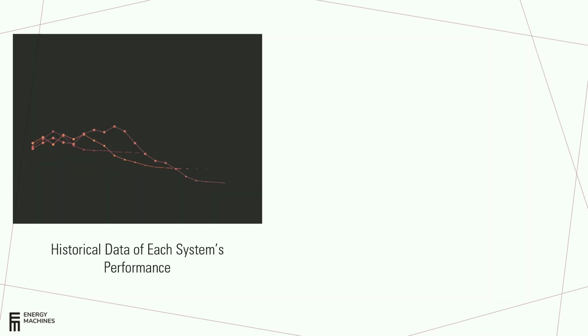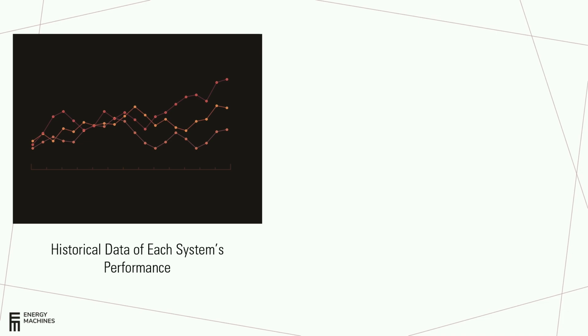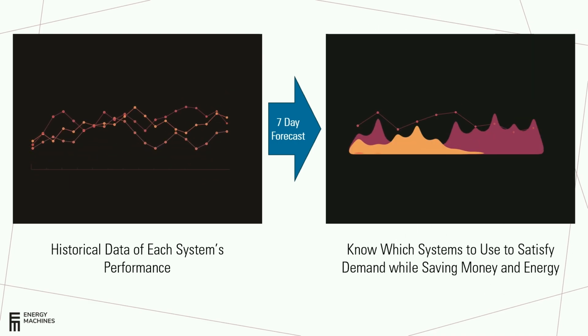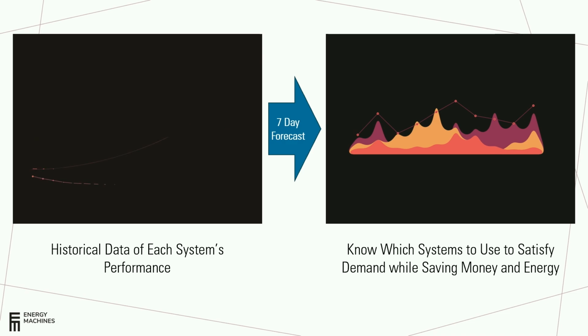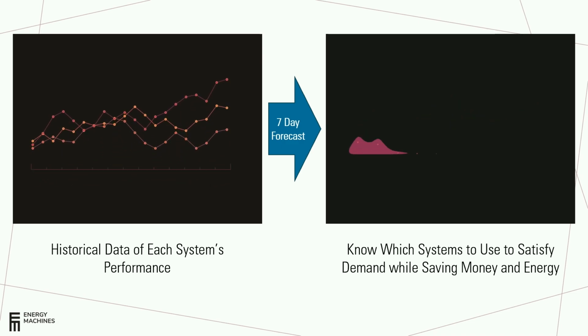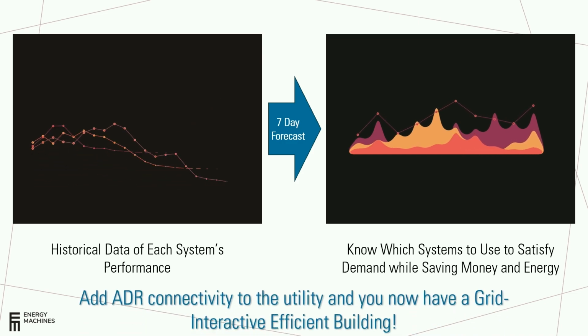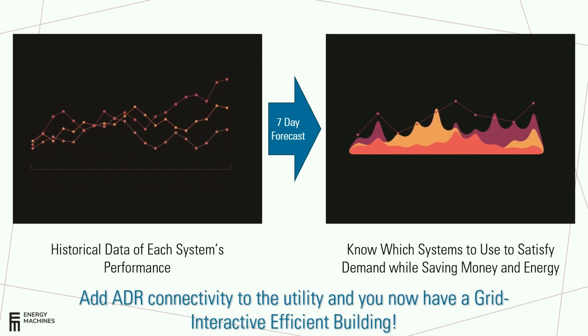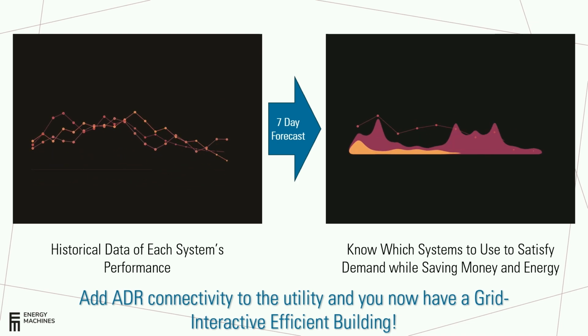So let's say you have your historical data of each system's performance during a specific given condition, and now you know the conditions coming with the 7-day look-ahead forecast. Now you can really start planning, saying geothermal will carry me through this whole thing, I don't need to do anything. Or maybe I need thermal storage, or maybe I need to start using the air source heat pumps. Now you have a very effective way of planning ahead, and when you start doing automated demand response and connectivity to the grid, you have a grid-interactive, efficient building. This gives utilities and buildings a way to maximize revenue potential, but also make the grid a lot more flexible.